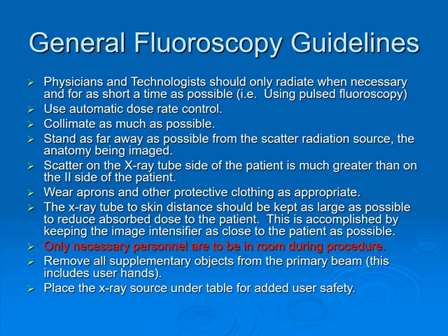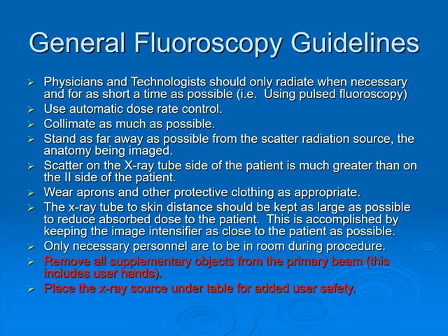Only necessary personnel are to be in the room during the procedure. Remove all supplementary objects from the primary beam. This includes the user's hands. And finally, place the X-ray source under the table for added user safety.